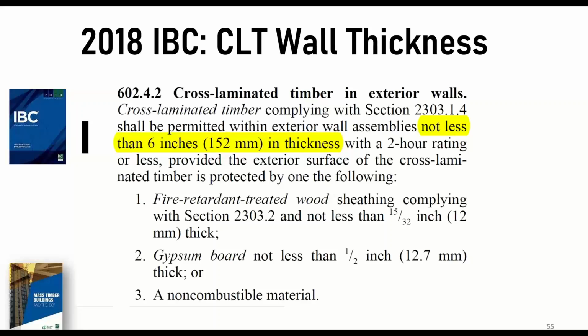And again, it provided clarification, the 4-inch minimum thickness of CLT versus the overall 6-inch thickness, and calling out the differences between the prior fire resistance. So now we're up to 2 hours of fire resistance to comply with E119. And the total wall assembly thickness has to be 6 inches with a minimum thickness of 4 inches associated with the actual cross-laminated timber component. So you can see we have that not less than 6 inches in thickness with a 2-hour wall assembly, still spelled out in 602.4.2.